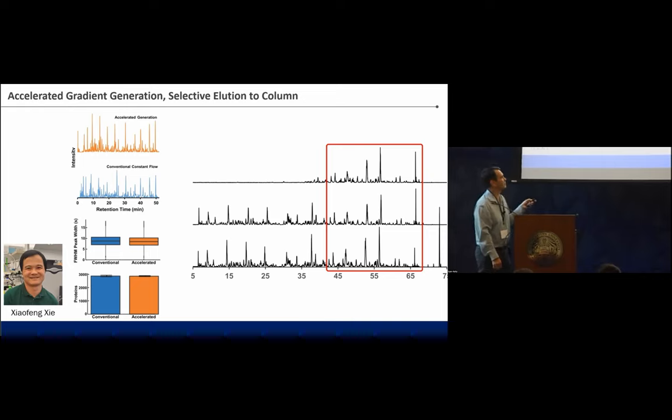Yeah, so we always have a trap column on our system. That trap column or solid phase extraction column is over here. We always have that. And the reason we do, you actually lose some of your sample this way versus a direct loading. But if we're working at 20 nanoliters per minute and we have a 1 microliter sample loop or something like that, it just takes too long. That's 50 minutes, I think, to transfer our sample from a direct sample loop onto the column.